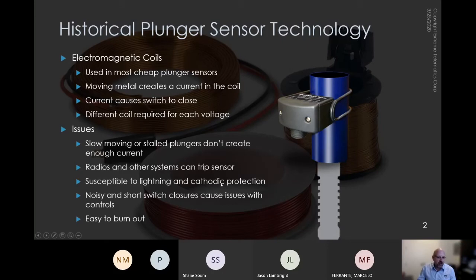But there come a lot of issues with this technology. Slow moving or stalled plungers, if they don't go by fast enough, that change in the magnetic field isn't picked up and you don't get an arrival signal. It can also act as an antenna for radios and other systems, tripping the sensor. Things like lightning can go through a field and take down a whole bunch of controls.